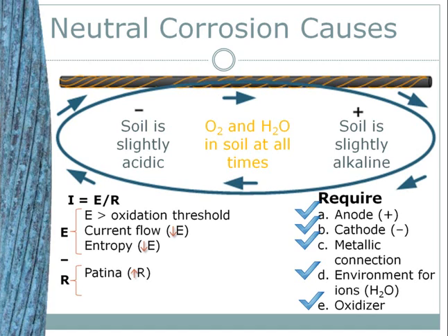Finally, there is the resistance of the neutral itself. As the neutral is consumed, the resistance of the loop increases. When individual strands are severed, the corrosion on those strands all but stops. This is why neutral corrosion is a consistently confined phenomenon — when we excavate neutral corrosion sites, the damage to the neutral is most typically concentrated within just a couple of feet. All five of these factors reduce the rate of corrosion as time advances.